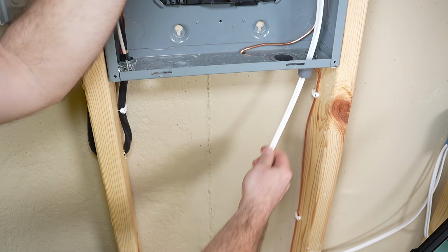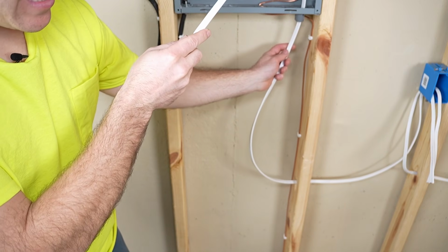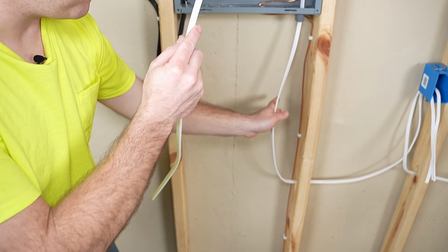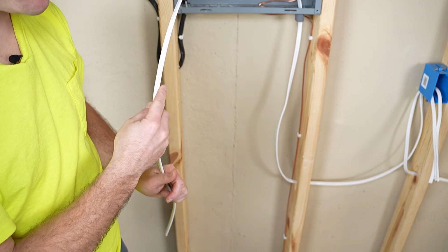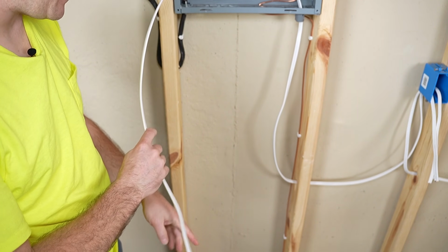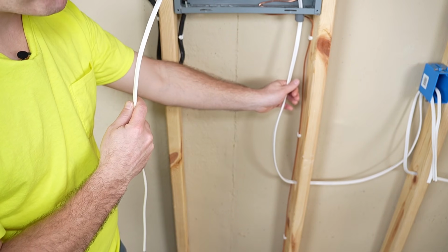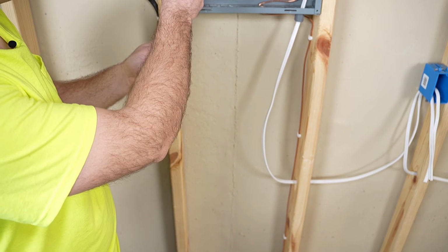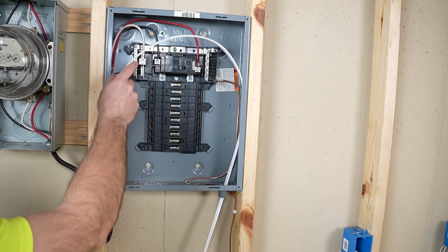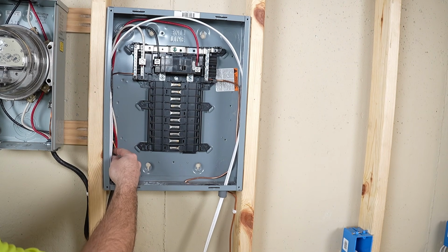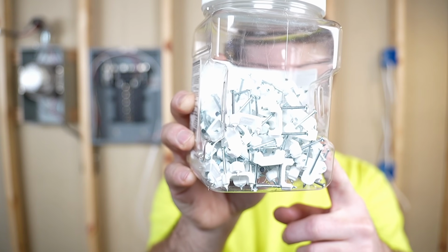So we'll get this wire all the way up in the panel, and I'm gonna leave a little bit of slack here because we still have to go through and do our strapping, which is what we're gonna do next. Once we get everything strapped, then we can pull these cables up a little bit tighter. For right now, I'm just gonna loop this cable up in the panel. That way it's out of my way. Next step is gonna be installing our wire staples.